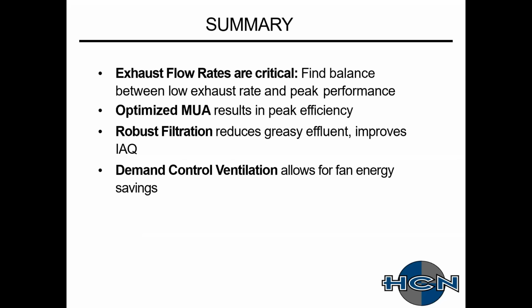Robust filtration. If we can capture as much grease at the source as we can, it's just going to promote a better and healthier environment in the kitchen itself, but also improve your duct and reduce the grease that's collecting up on the roof. Typically, there's a grease cup on most of the power ventilators. I ask most of the maintenance people that go out there to take a look at those. Those typically never get filled, and what happens is you get a rain or something like that, it fills up and you have grease all over the roof.